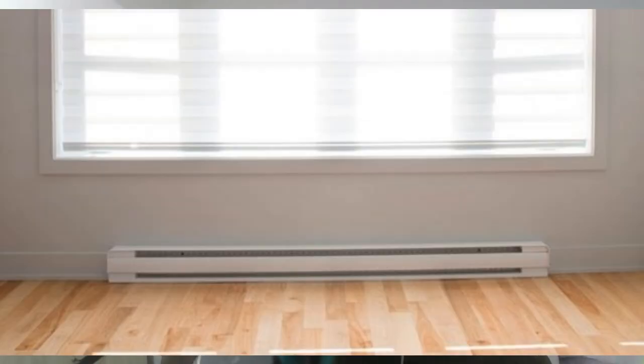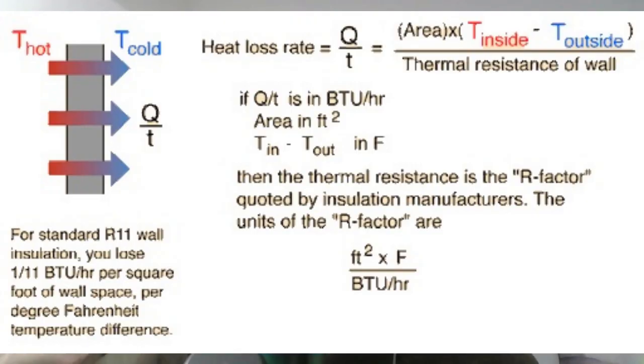The next one bothers me even more, and it's so pervasive in how Canadian homes are designed and built. It is normal to have baseboard heaters installed along the walls, in particular under windows. The walls are what separates your home from the cold. The larger the temperature difference, the faster the heat loss, and by heating the walls first, it ensures the walls are the hottest part of the room, maximizing heat loss. Even worse when you think about the under window ones, where the insulation factor is probably the worst. And insulation doesn't stop heat loss, it just slows it down.